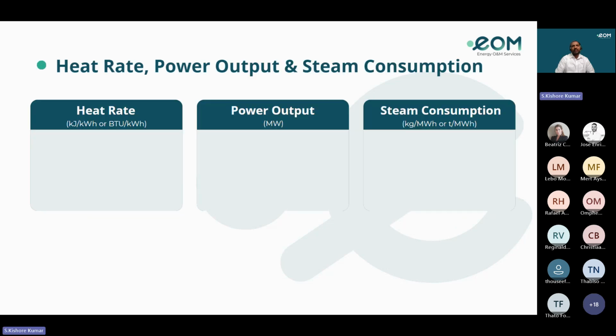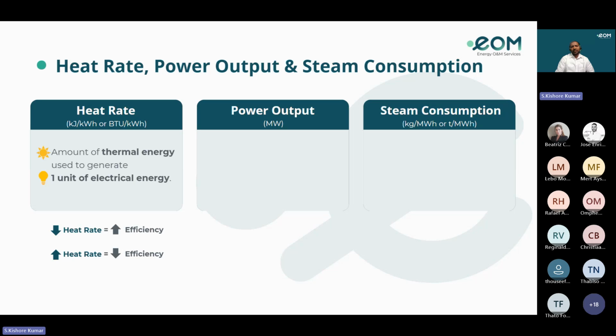So what is heat rate, what is power output, and what is the steam consumption? What is the heat rate? Think of it as how much energy we need to make 1 unit of electricity. A lower heat rate means higher efficiency, less fuel needed, and lower cost. A higher heat rate means lower efficiency and more fuel wasted. For example, if a turbine has a heat rate of 9,000 kilojoules per kilowatt hour, it means it needs 9,000 kilojoules of heat energy to make 1 kilowatt hour of electricity.